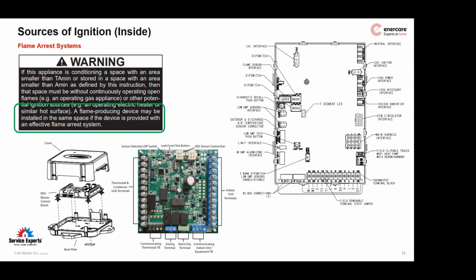Carrier is not going to have that, so I don't know what you primarily are installing for when you're putting this stuff in. Carrier's is always going to be an external board with basically an 8-foot whip with labeled connections. So you'll bring your thermostat wire into the new box. It'll look very similar to what Lennox has here. Their cover is clear or opaque. And then there's going to be an 8-foot kind of snake that you'll tie into the furnace that's already pre-labeled. You just bring the labeled connections into the connections of the furnace control board or air handler control board.